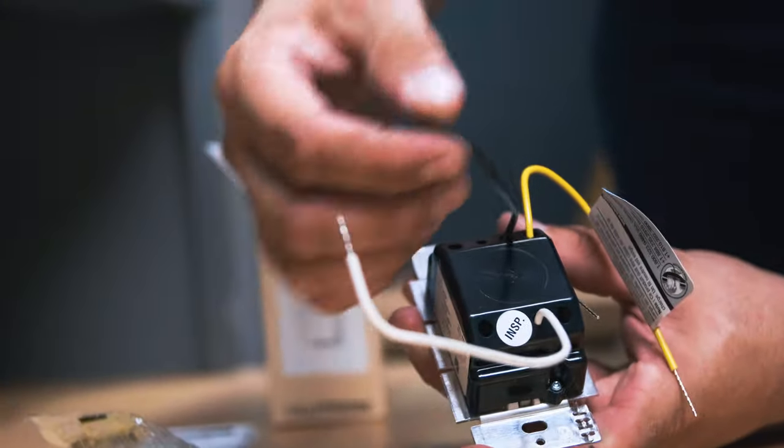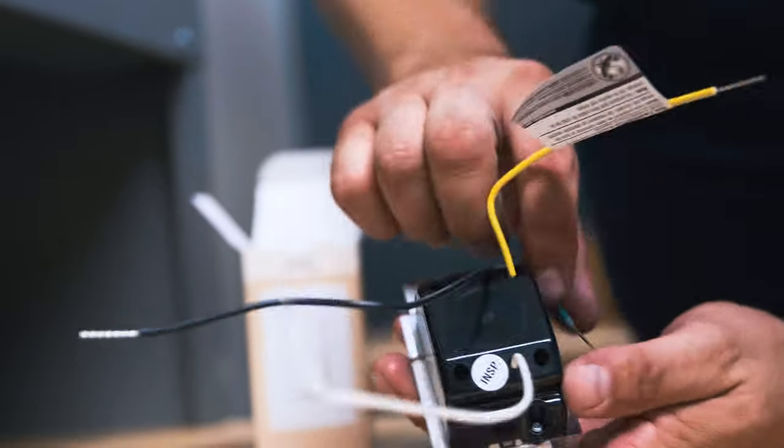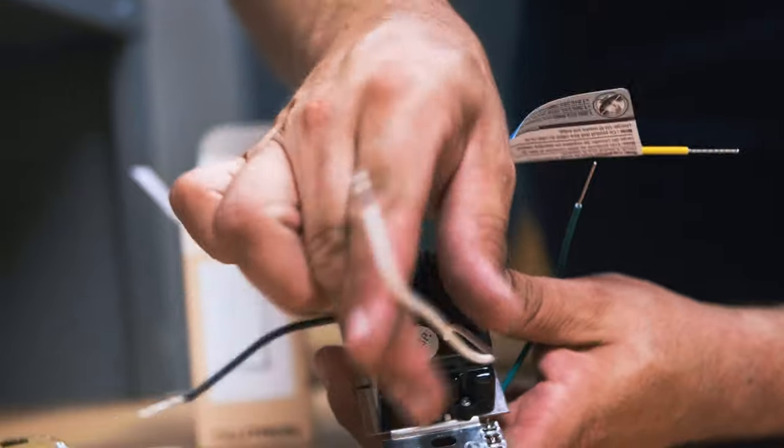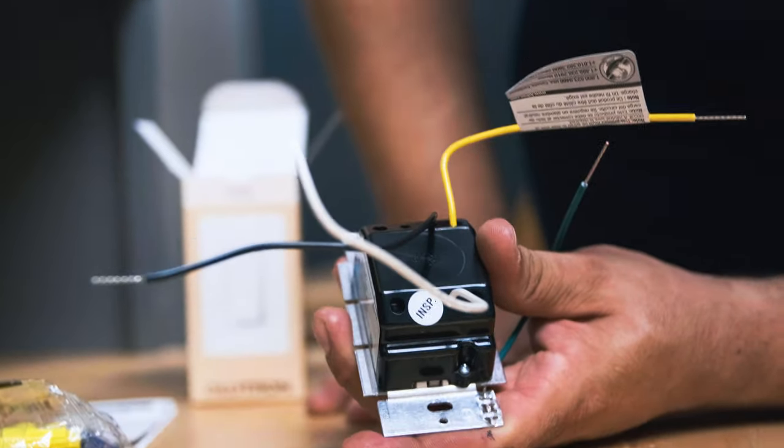This one has a hot. This goes to your line side. This yellow wire goes to your load. There's that green for ground. And then this one requires a white neutral connection in the box. So this is for the ELV.